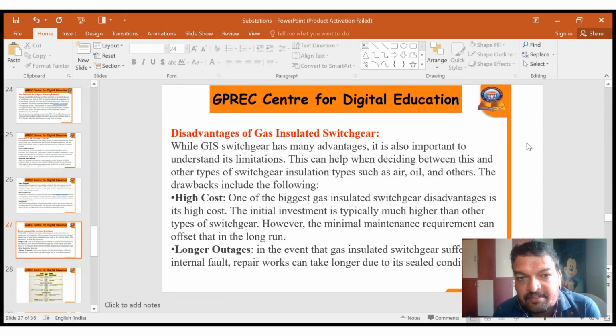Next, coming to the disadvantages of gas insulated switchgear. Though we have advantages like being more reliable, compact design, and less maintenance required as compared to the air insulated substation, the main disadvantage is high cost. One of the biggest disadvantages of gas insulated switchgear is its cost. The initial investment is typically much higher than other types of switchgear. However, the minimal maintenance requirement can offset that in the long run. When we compare with other switchgear substations, the initial investment for installing gas insulated switchgear is much higher than the remaining substations. Because of this, it leads to a higher cost.